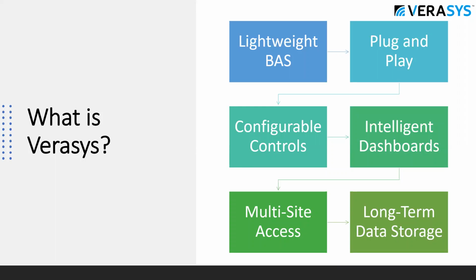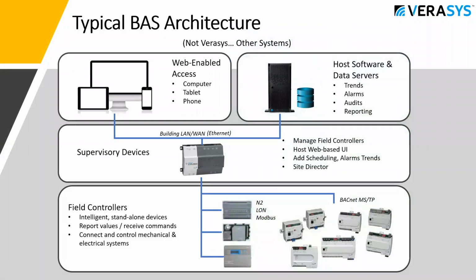Moving on here, this is a diagram that shows a typical BAS architecture. This is not Verasys. In this example, I have an FX controller, so this would be a Niagara system. But this could be anything — it could be an FX, it could be a Honeywell Webs or a Distech. Regardless, this is a typical configuration for your Niagara system.